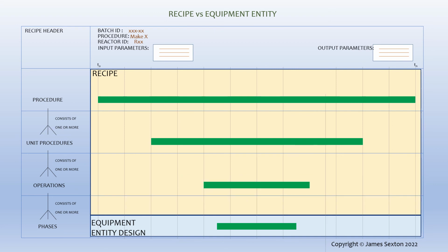Going back to the most flexible configuration, consider the makeup of each procedural element. Each one can receive some input parameters and a start command. Each can report back some output parameters and a completion status. Finally, each has a sequential part that organizes its subordinates.